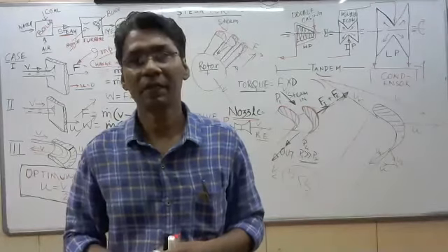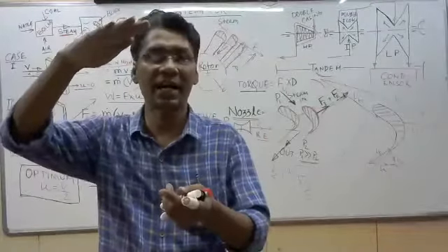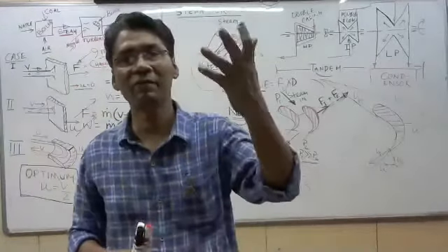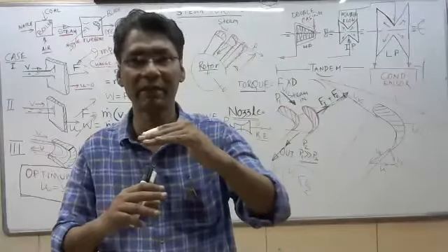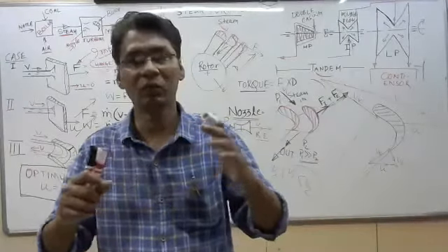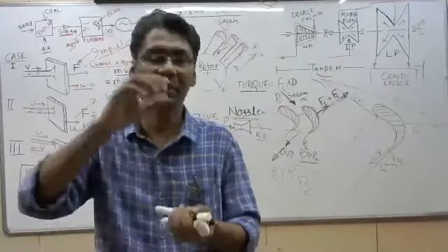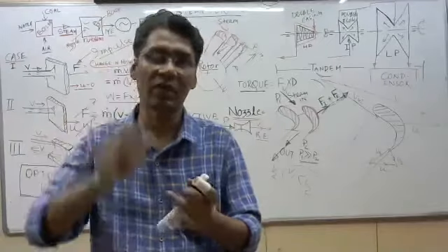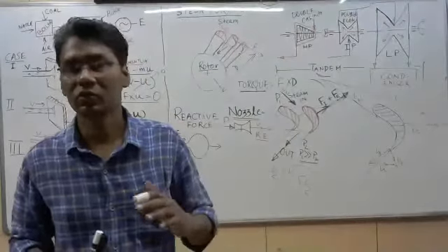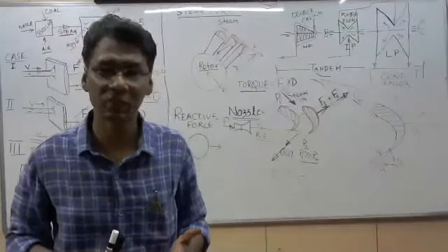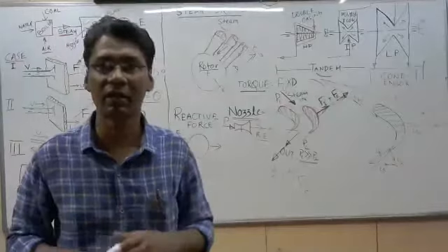Double casing turbine is designed. If the casing thickness is higher, it will take a lot of time for heating or starting. To minimize the turbine starting time and heating time, we design the high pressure turbine as a double casing type. With double casing, the casing thickness becomes lower. The detailed discussion cannot be done within 1 hour. So to avoid expansion issues and to reduce the heating time of the turbine, we design the double casing type.